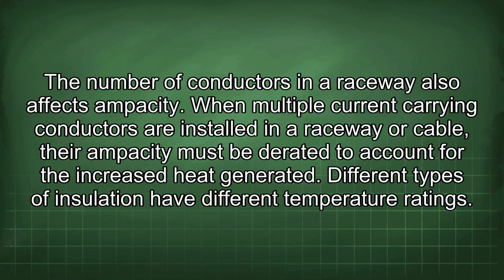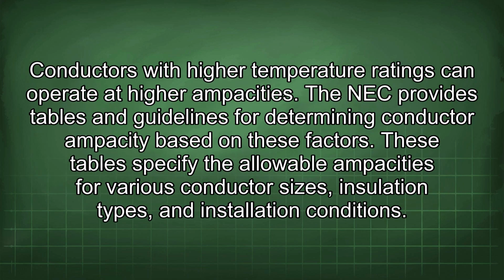When multiple current-carrying conductors are installed in a raceway or cable, their ampacity must be derated to account for the increased heat generated. Different types of insulation have different temperature ratings. Conductors with higher temperature ratings can operate at higher ampacities. The NEC provides tables and guidelines for determining conductor ampacity based on these factors. These tables specify the allowable ampacities for various conductor sizes, insulation types, and installation conditions.